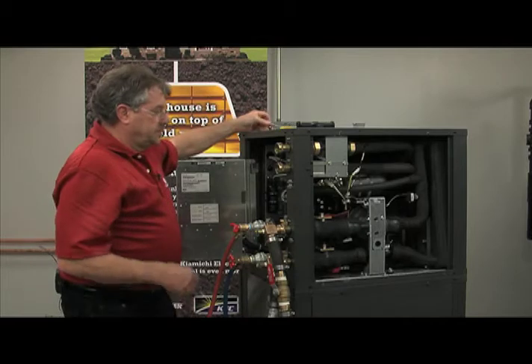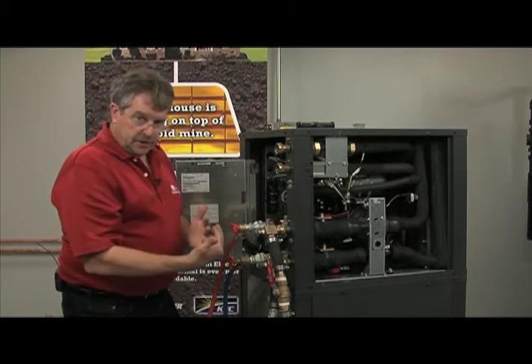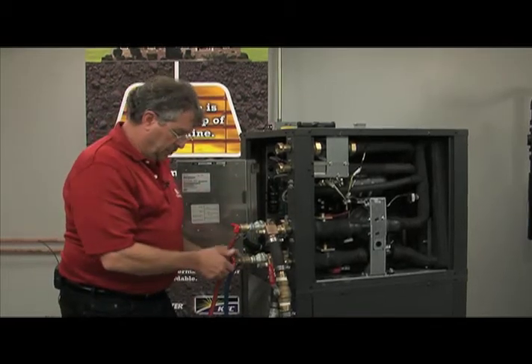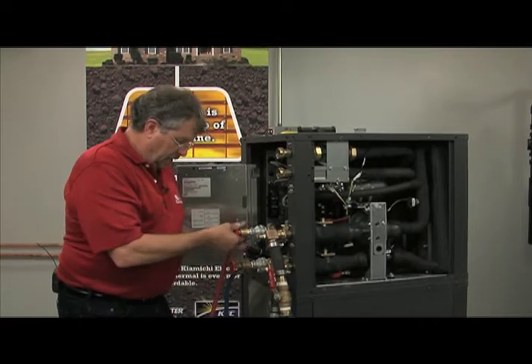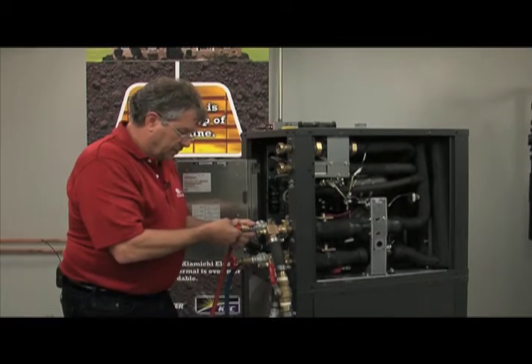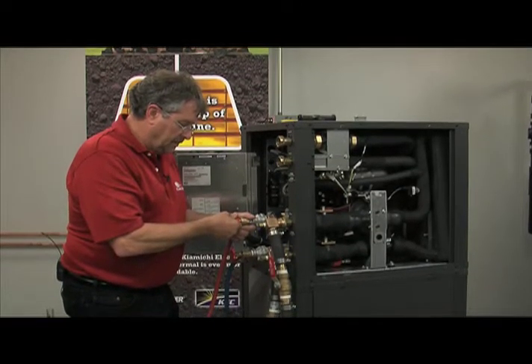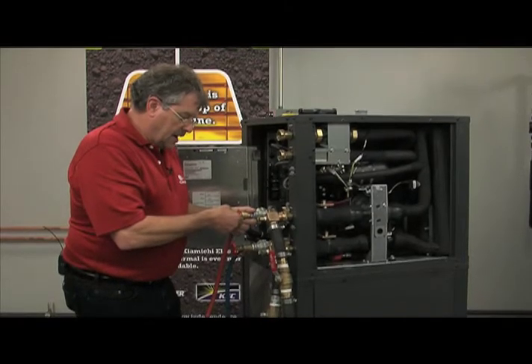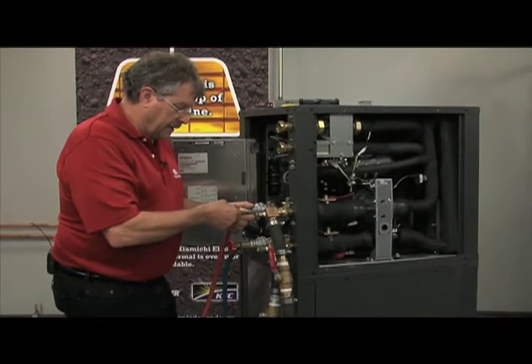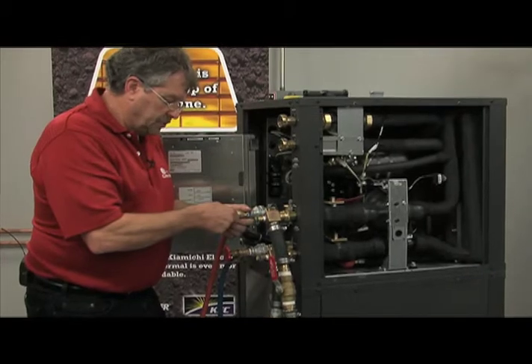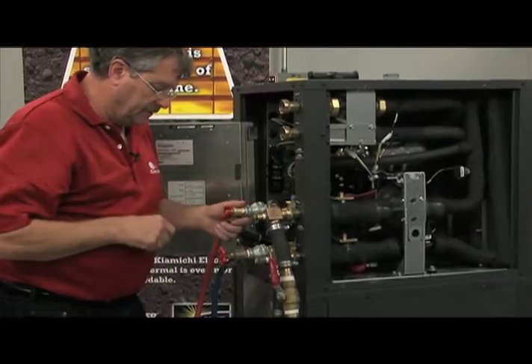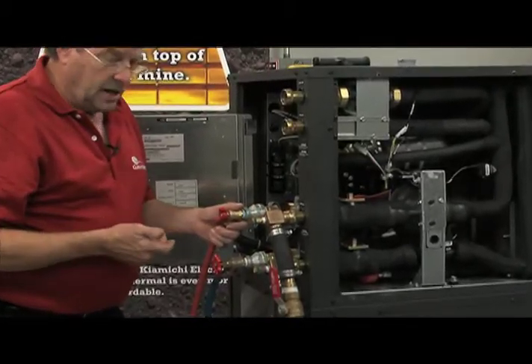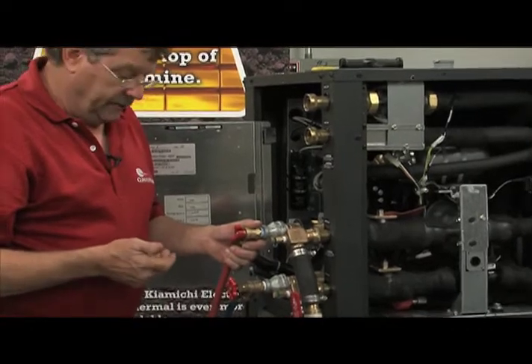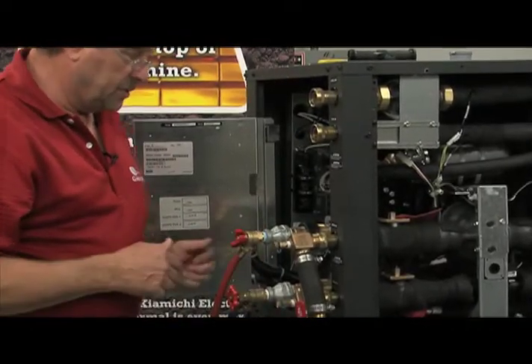So I've now oriented it so that my loop is isolated, and I'm open now to the heat pump. I'm going to go ahead and take that pressure off the interior of the heat pump. Because I may have to take out that expansion tank, I've left that valve open so I can also displace the fluid that is captive in there. It's not a lot of fluid, but give it a few moments. Make sure that you've drained that pressure out.